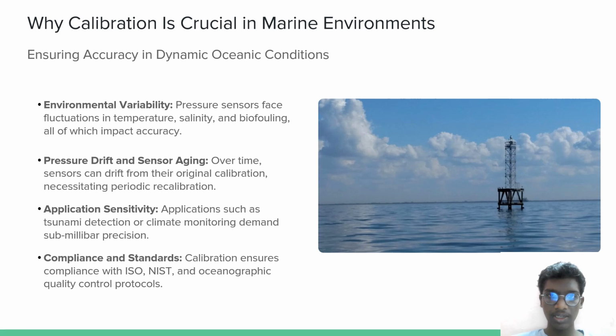Why calibration is crucial in the marine environment, ensuring accuracy in dynamic oceanic conditions. Environmental variability: pressure sensors face fluctuations in temperature, salinity, and biofouling, all of which impact accuracy. Pressure drift and sensor aging: over time, sensors can drift from their original calibration, necessitating periodic recalibration. Application sensitivity: applications such as tsunami detection or climate monitoring demand sub-millibar precision. Compliance standards: calibration ensures compliance with ISO, NIST, and oceanographic quality control protocols.